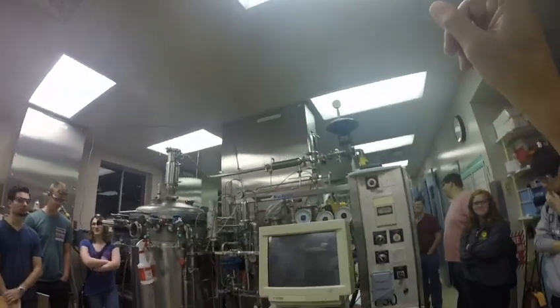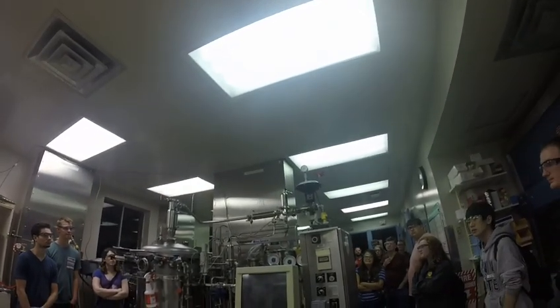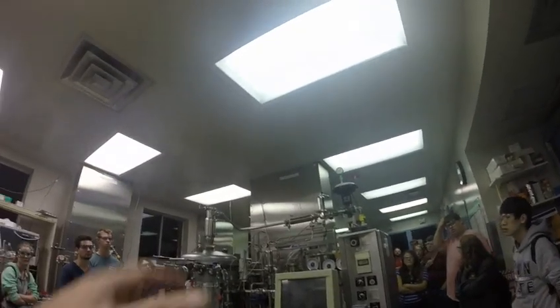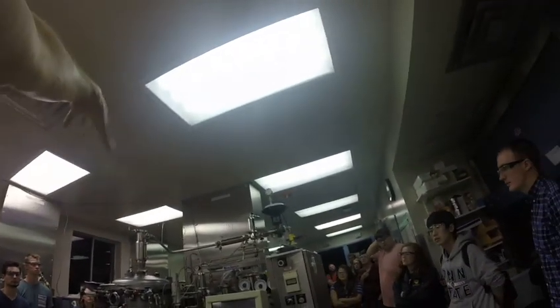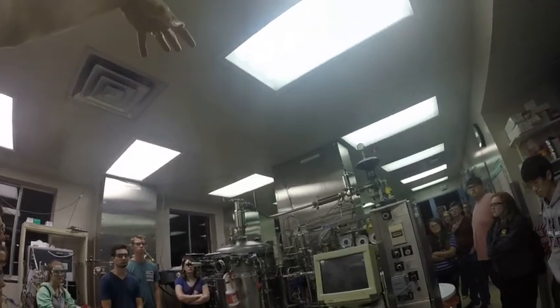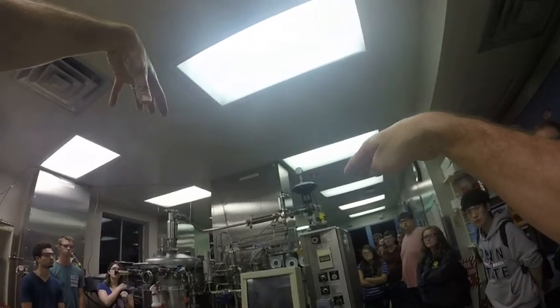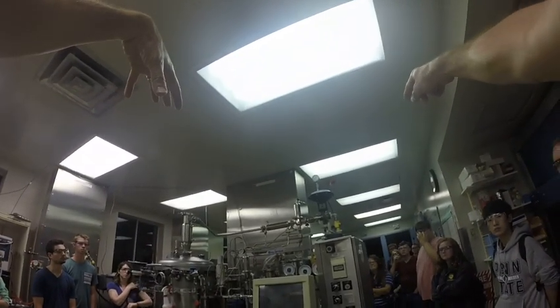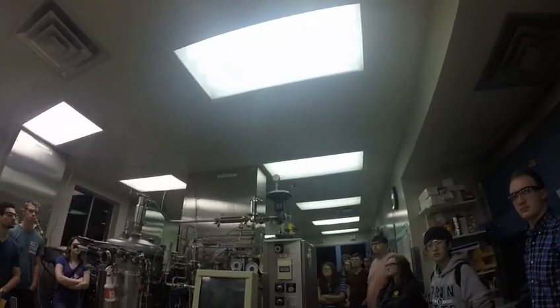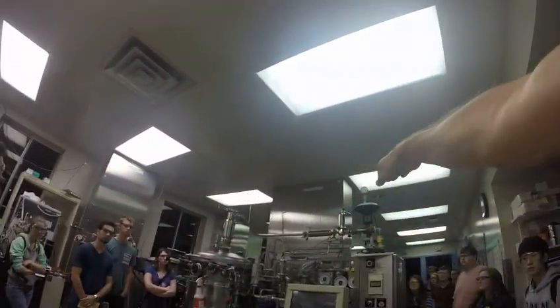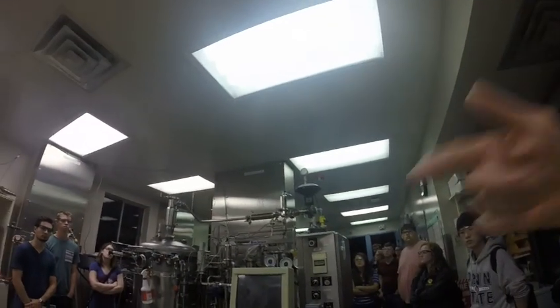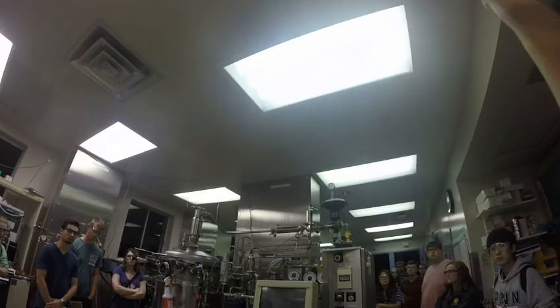So the question then is, what is it functioning as if it's not a pre-filter? What it's doing in the back is acting as a heater. We tried to drop out as much as we could in the condenser and cooled the gas, but we're very close to saturation. We can't have that going into the microbial filter, so we need to heat the gas back up, well above the point where condensation can take place, before it goes through the actual microbial filter.